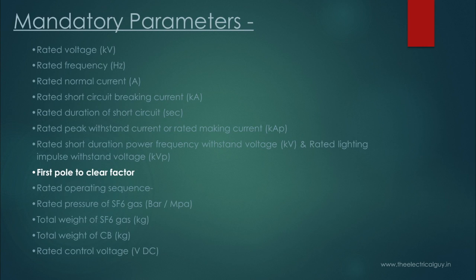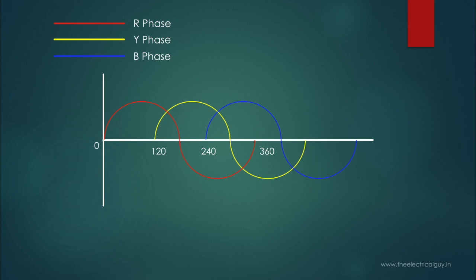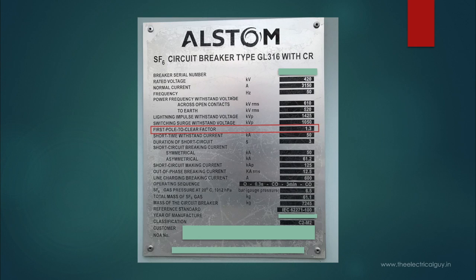First pole to clear factor: in a 3-phase circuit breaker, arc extinguishes during current zero. Because currents are out of phase by 120 degrees in a 3-phase AC circuit, current interruption is not simultaneous — contact of one pole will open before the other two. The power frequency recovery voltage across the first pole to open is therefore more than the others, and this is called the first pole to clear factor. It is given as a multiple of the normal system voltage; on the nameplate it is mentioned as 1.3, meaning the first pole to open will have 1.3 times the normal system voltage across it.